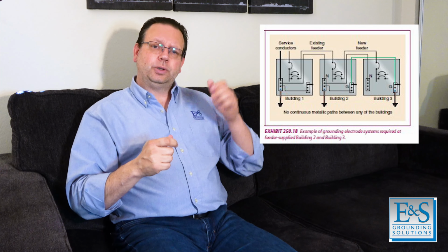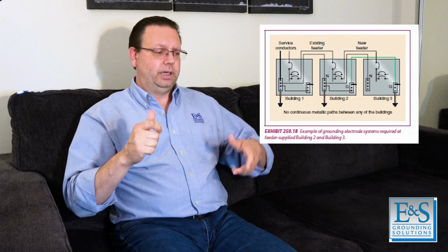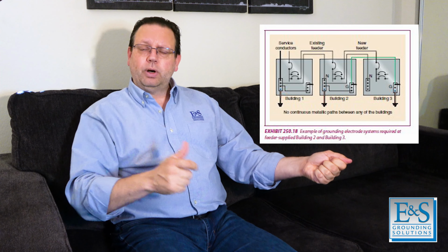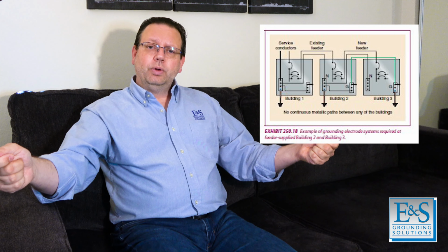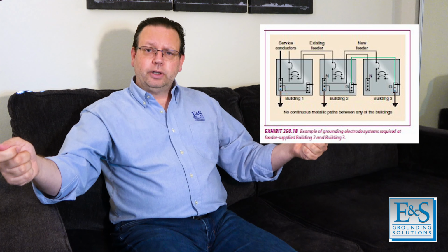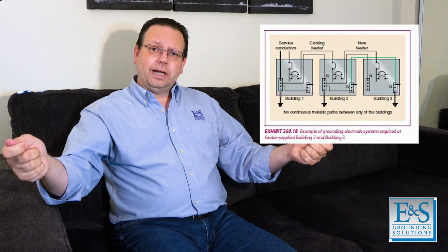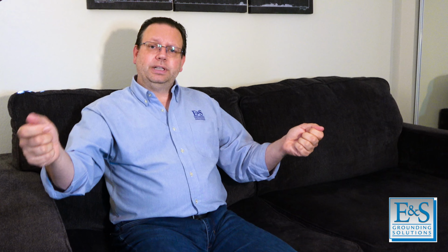If you went up to that source transformer, took your ohm meter, and measured over to your panel, and it's high, well, that means there's probably nearly an open, so probably no metallic connection between the two. But if it's low, it might be because the ground rods touch the steel rebar or there's some other connection happening.